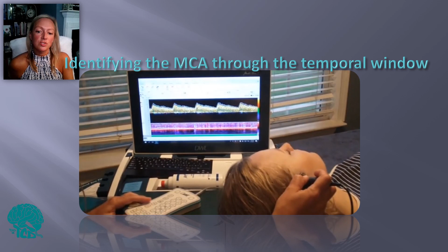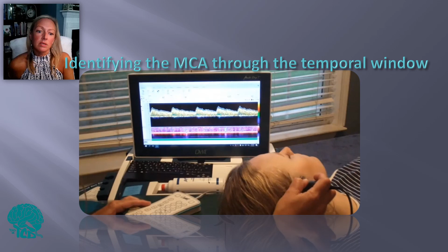I won't start taking pictures initially at this point. I will make sure all my parameters on the screen are where I want them. You'll need to know how you have your scale, your power, your filter. You'll need to isolate all of those parameters and adjust them appropriately. And you will angle your probe to find the most optimal signal, ensuring you are capturing your highest mean flow velocities. And then you will walk your sample volume or cursor through the length of the vessel and capture images or pictures depending on the institution's protocol, ideally at 4 or 5 millimeter increments with images taken throughout the whole length of the artery, which is sufficient for our subarachnoid hemorrhage patients.